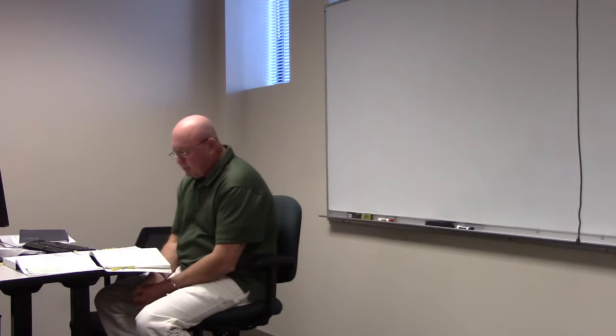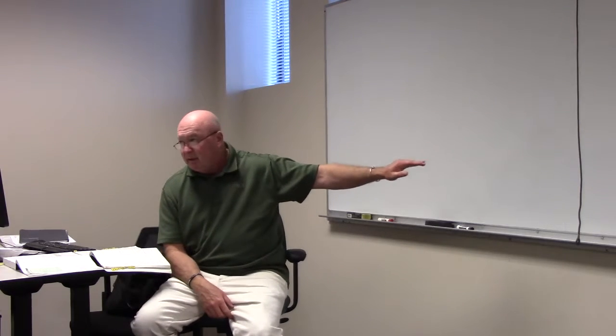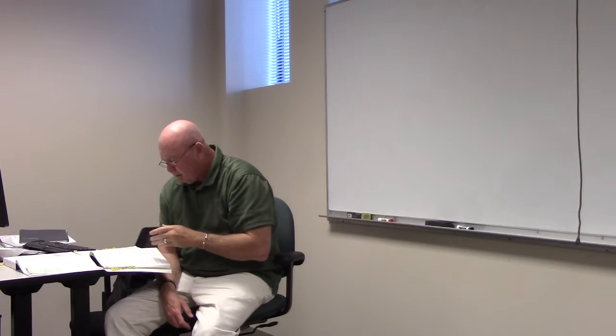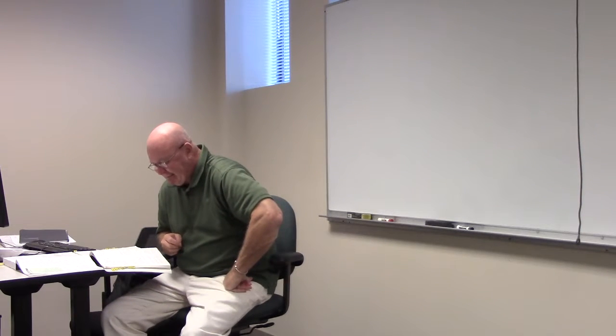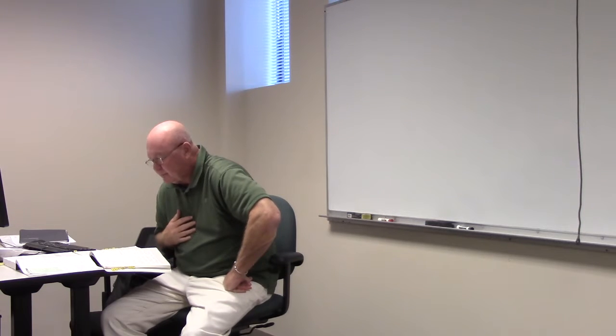Like, this is a good example. 220.44 says receptacle loads calculated in accordance with, and you have to go back to 220.14 H and I to see what it says. Shall be permitted to be made subject to the demand factors given in. Now, there's another demand factor table there, 220.42. You see that there? See, Table 220.42 is the lighting demand factor, and that's what we were doing earlier. Let's just take, like, a store. What would a store be on? If we were doing a retail store, what would a retail store fall under in Table 220.42? Which category? All others? All others. Exactly. How about a school? All others? All others, yeah.